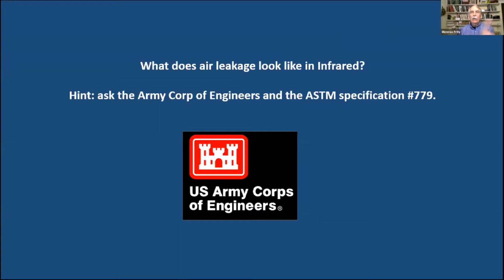But curiously, we're talking about what does an air leak look like. When you go perform these kind of tests, which we've done over 200 of them at TSI for the U.S. Army Corps of Engineers, we find that we're always required to go into that building under ASTM specification 779, which simply says you're going to go in there with thermographic capabilities. You do have to go in there with infrared capabilities, because if there happens to be an air leak, they know that infrared is one of the easiest tools to use to help find air leaks. So we've actually got this process of looking for air leaks with infrared endorsed indirectly by the Army Corps of Engineers.